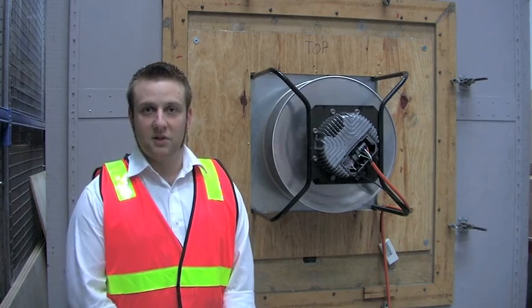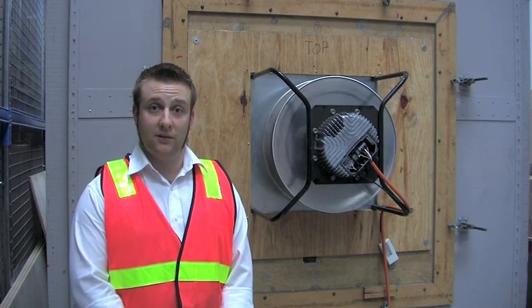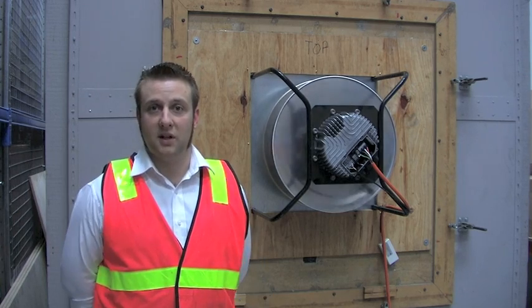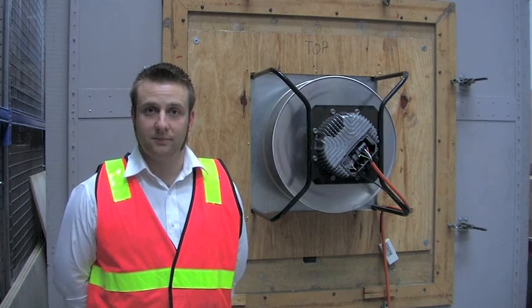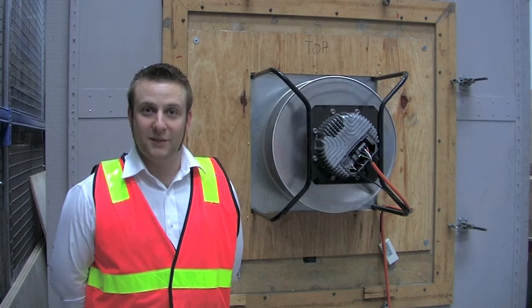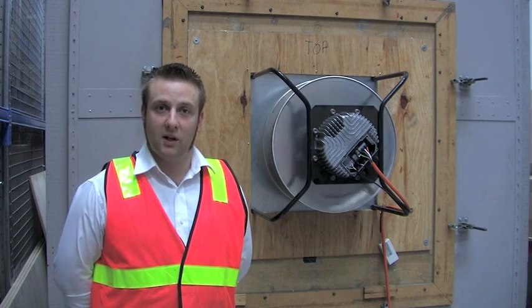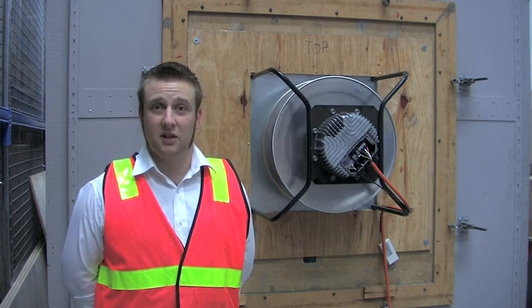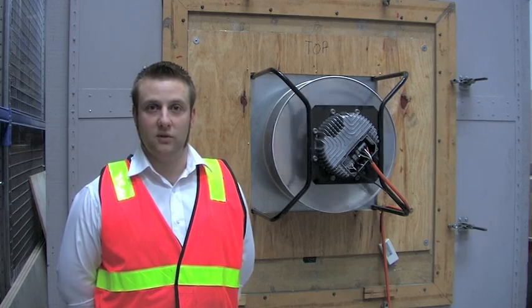The test rig can measure from 70 meters cube per hour to 11,000 meters cube per hour in terms of airflow and from zero to a thousand pascals in static pressure. This means we can test from our 190 millimeter diameter fans right up to some of our 630 millimeter backward curved centrifugal.